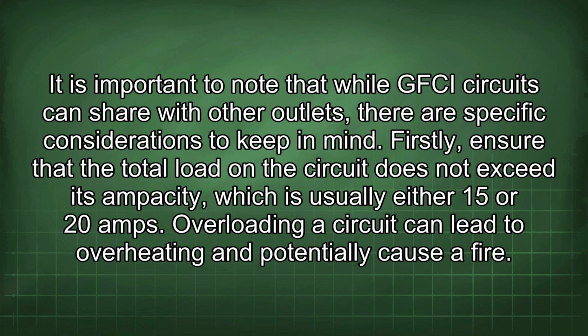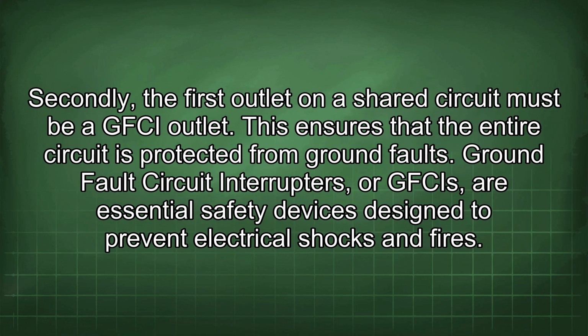It is important to note that while GFCI circuits can be shared with other outlets, there are specific considerations to keep in mind. Firstly, ensure that the total load in the circuit does not exceed its ampacity, which is usually either 15 or 20 amps. Overloading a circuit can lead to overheating and potentially cause a fire. Secondly, the first outlet on a shared circuit must be a GFCI outlet. This ensures that the entire circuit is protected from ground faults.